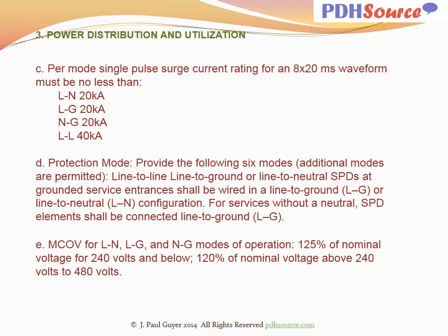Surge protection devices at grounded service entrances shall be wired in a line to ground or line to neutral configuration. For services without a neutral, surge protection device elements shall be connected line to ground. MCOV for LN, LG, and NG modes of operation are 125% of nominal voltage for 240 volts and below, 120% of nominal voltage above 240 volts to 480 volts.